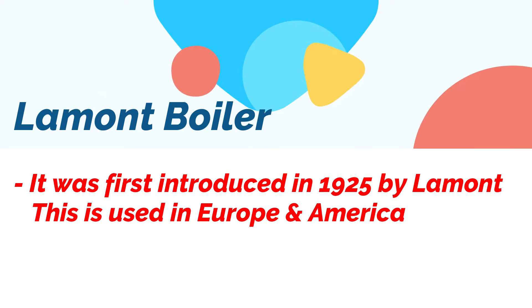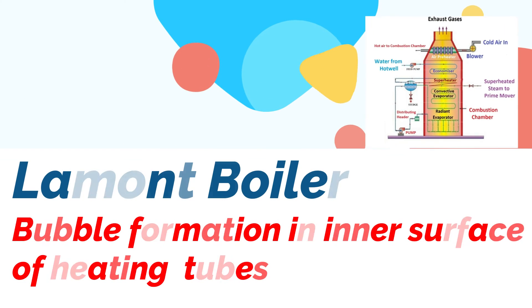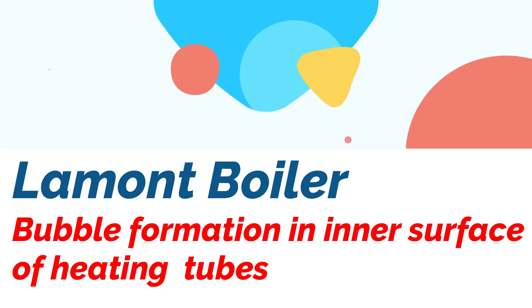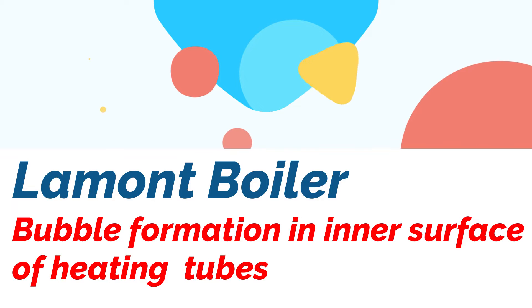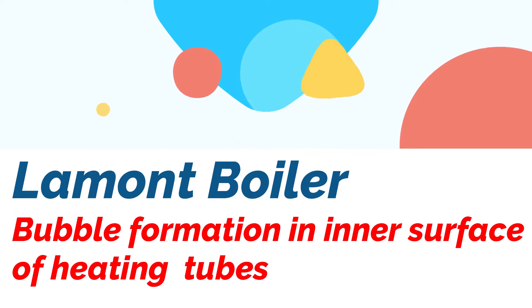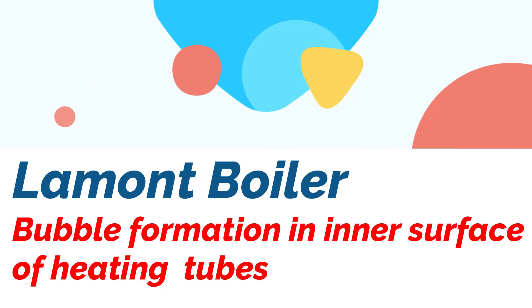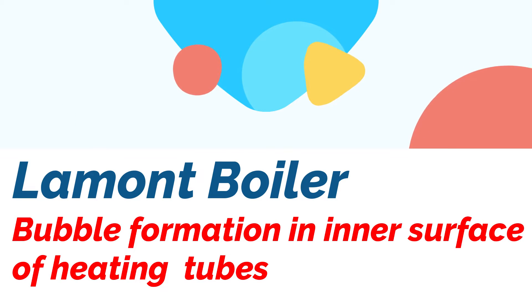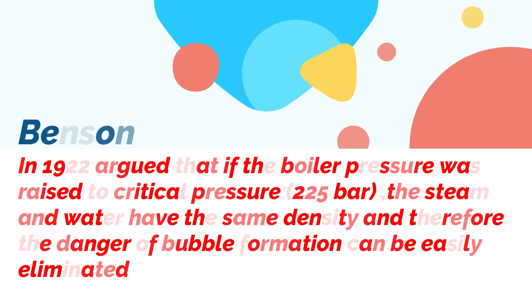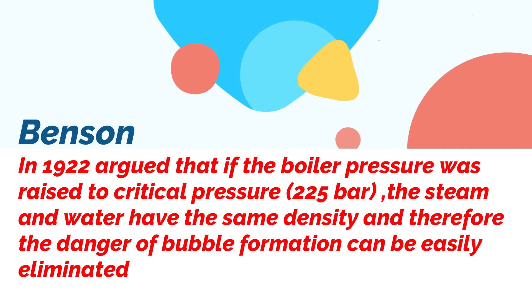The main difficulty experienced in the Lamont boiler is the formation and attachment of bubbles on the inner surface of heating tubes. The attached bubbles reduce the heat flow and steam generation as they offer higher thermal resistance than the water film.